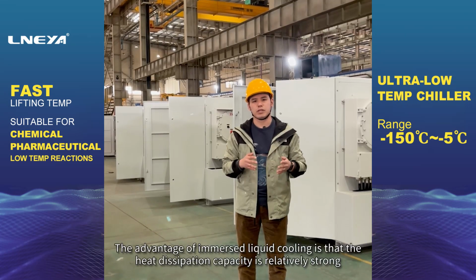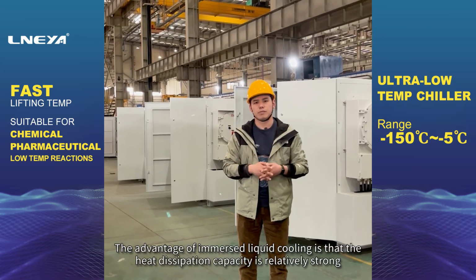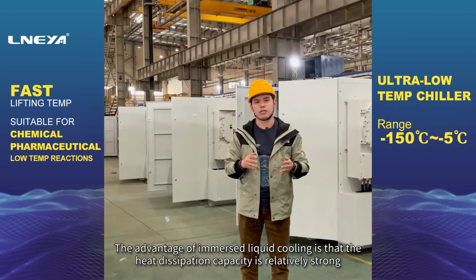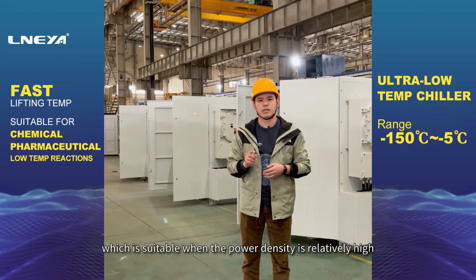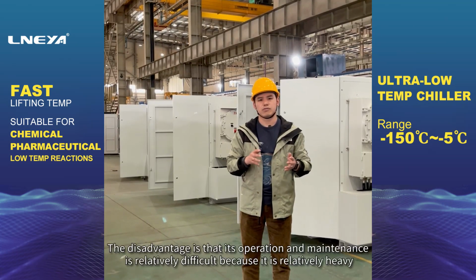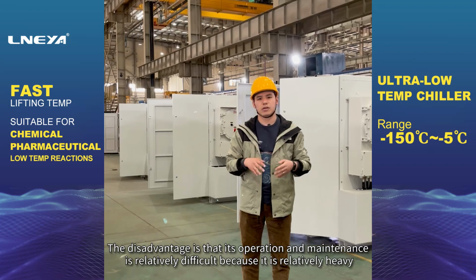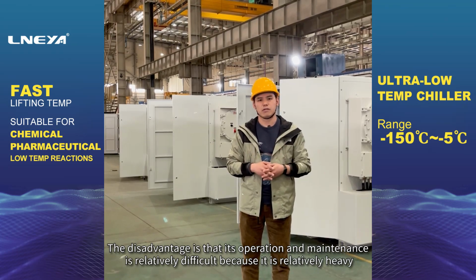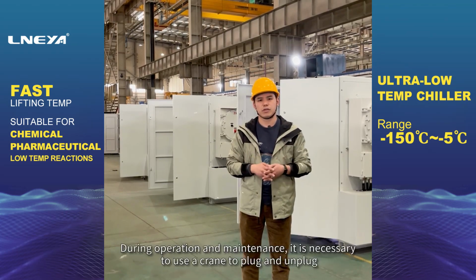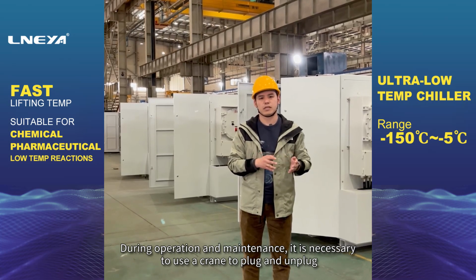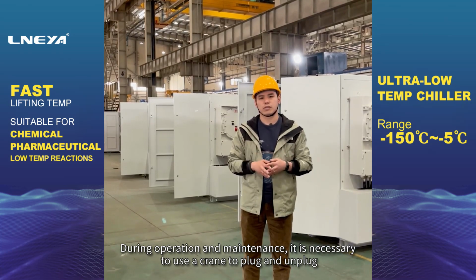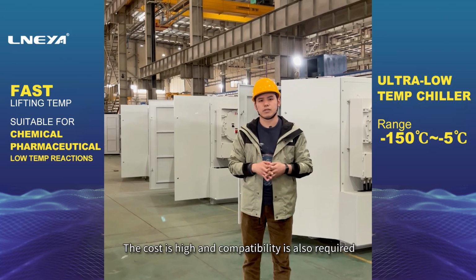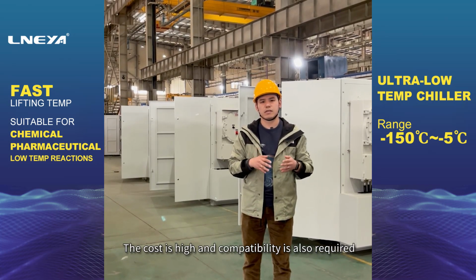The advantage of immersion liquid cooling is that the heat dissipation capacity is relatively strong, which is suitable when the power density is relatively high. The disadvantage is that its operation and maintenance is relatively difficult because it is relatively heavy. During operation and maintenance, it is necessary to use a crane to plug and unplug. The cost is high and compatibility is also required.